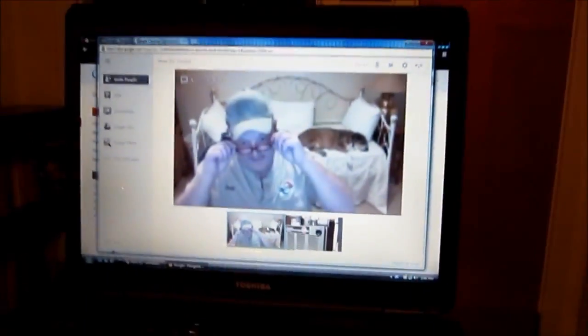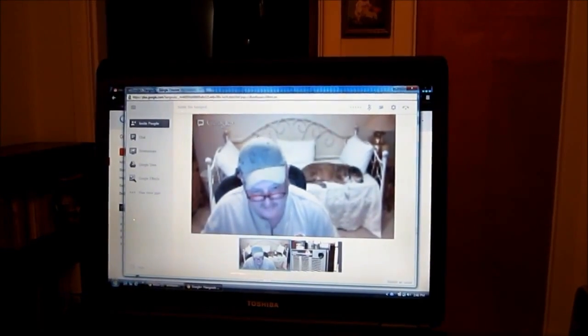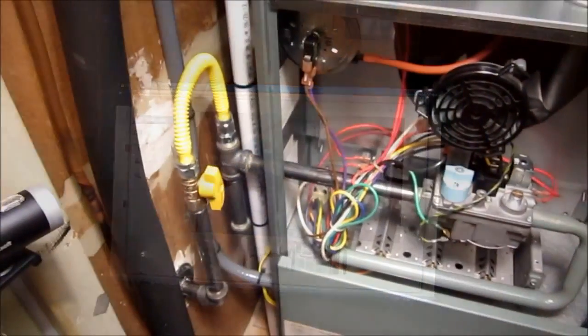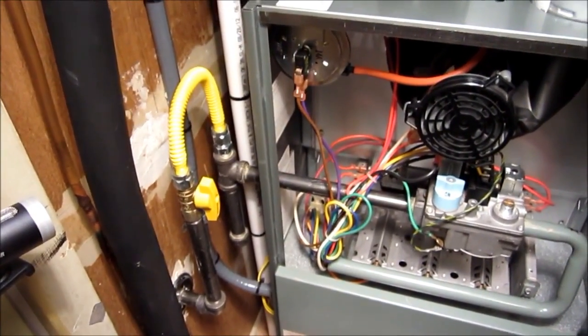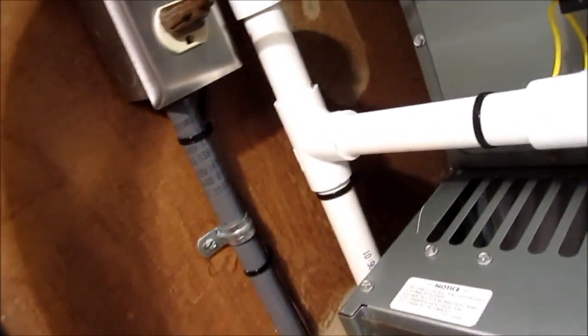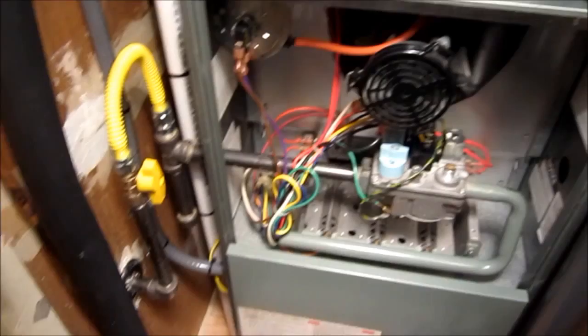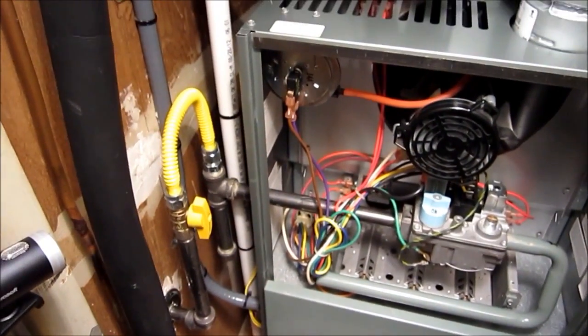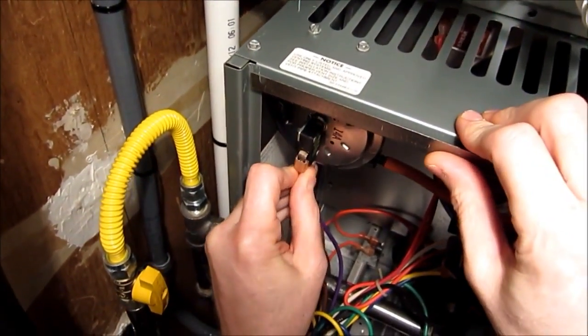All right Ray, let's pop that door off. First thing we're going to do is test it electrically before we pull the manometer out. Ray, make sure the power is off at the disconnect up there. Yes, it's off. Okay, fantastic. We're going to check for a shorted pressure switch. With the power off, I want you to remove the leads off your pressure switch right there.